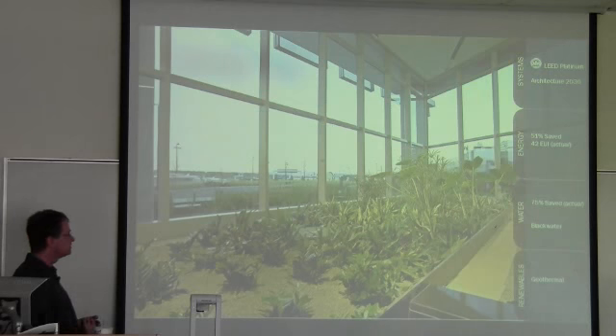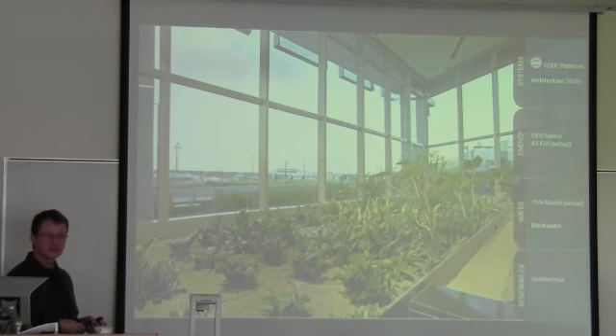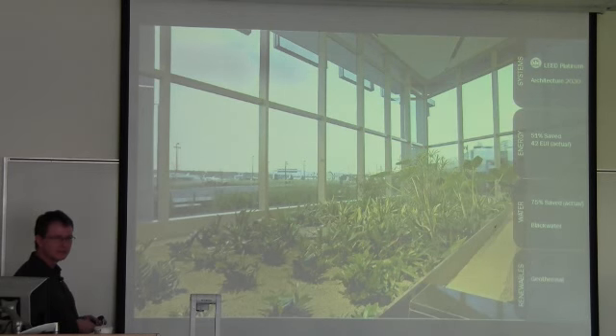Eco-districts are considering living machine type applications because they're fairly compact. This system was designed to treat 5,000 gallons per day. It's currently treating about 3,000 gallons. So it's a little under capacity right now, but we have some reserve capacity that we're planning if there's more systems in the future that want to be sourced for this. So it's scalable, and it's also something we're working on with their neighbors next door.